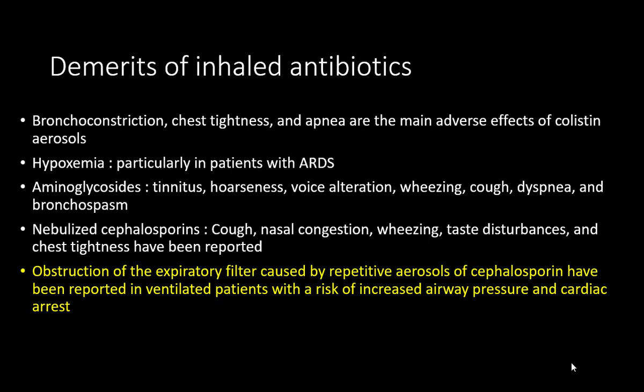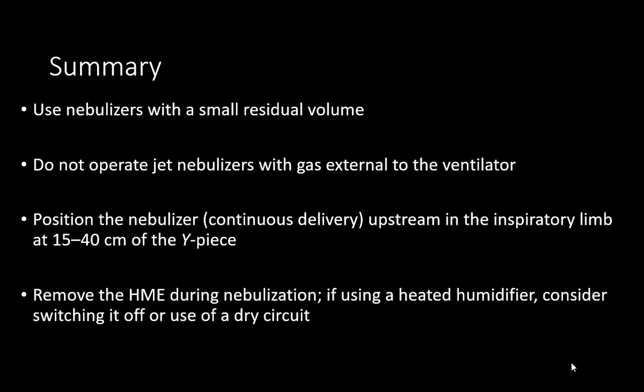So, just to summarize: use nebulizers with small residual volume, which means please do not use jet nebulizers. Do not operate jet nebulizers with gas external to the ventilator. Position the nebulizer upstream in the inspiratory limb, 15 to 40 cm from your Y-piece. Remove the HME during nebulization, and after nebulization, please do not forget to reconnect it, otherwise you are giving dry air.